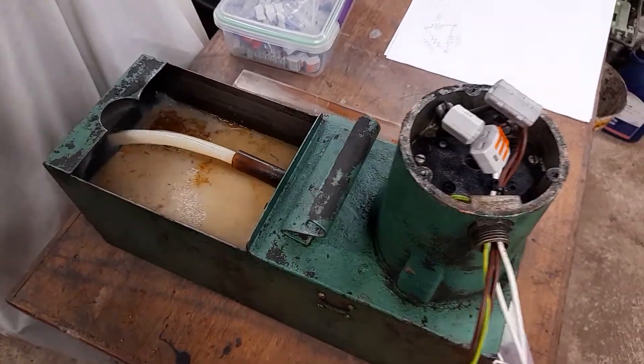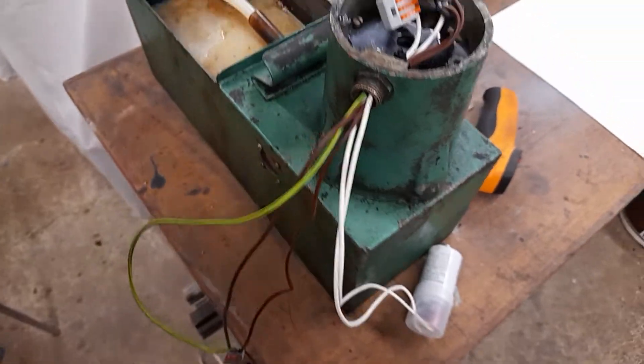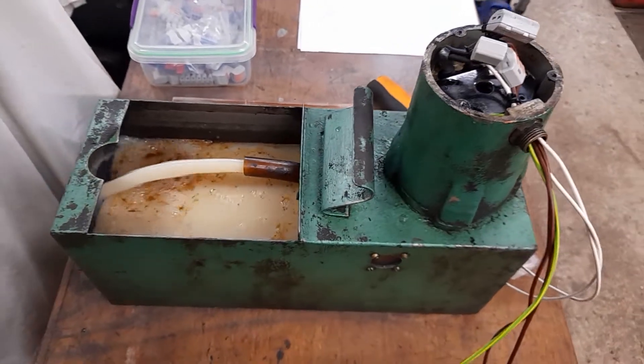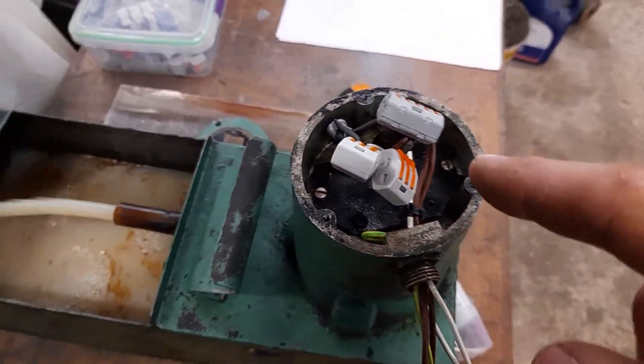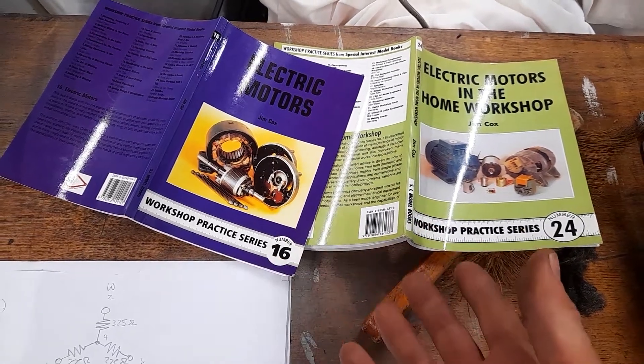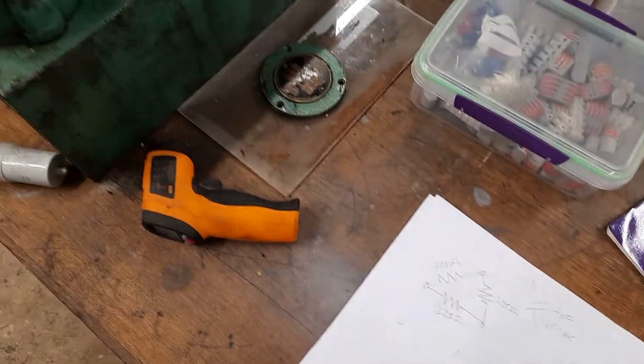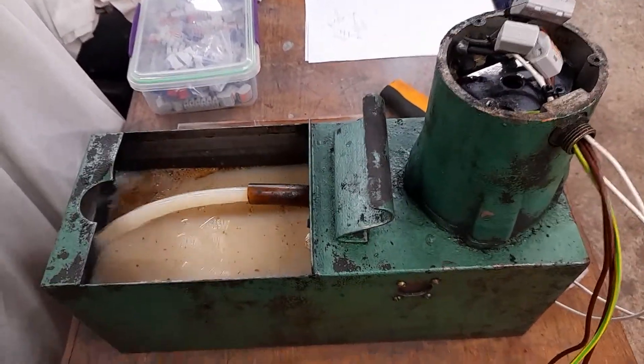You're looking at a three-phase Colchester lathe coolant pump running purely off single phase — no variable frequency drive or additional electronics involved, other than a capacitor which I've added across one of the windings. In this video we're going to look at the motor, the wiring, and I'll give you a couple of references so you don't have to take my word for it.